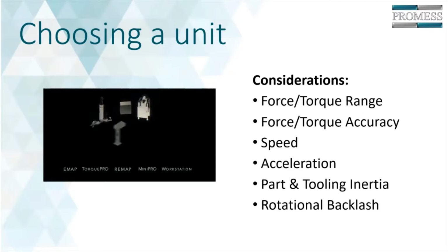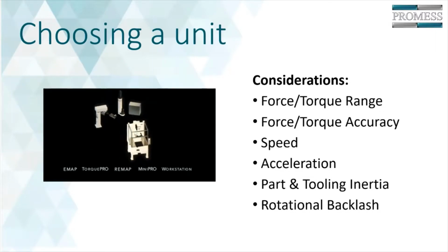Part and tooling inertia—this is a big consideration for torque units especially. A torque actuator needs to be able to control the rotating load accurately to prevent oscillations or overshoot. One issue we see somewhat often is heavy tooling on a relatively low torque unit. Providing even a ballpark part tooling inertia to the manufacturer during the selection process can simplify the overall setup and improve long-term functionality.